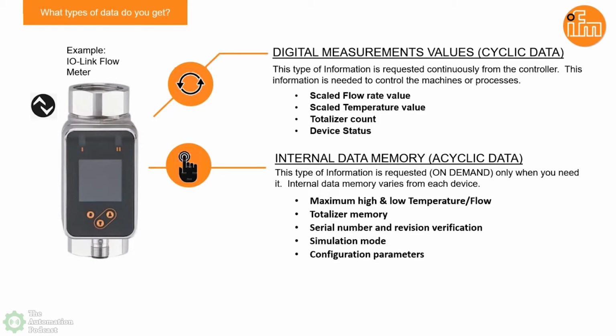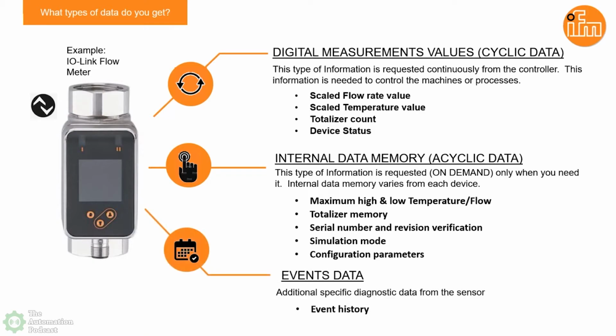This can be specific for every type of IOLink sensor in the market. We also have another subsegment, which we call events data. This is related to even more specific diagnostic data for the sensor, so we'd be able to get this back into the PLC with some kind of error code or diagnostic data that we could bring in and monitor. These are three different data sets that we can get from an IOLink device.